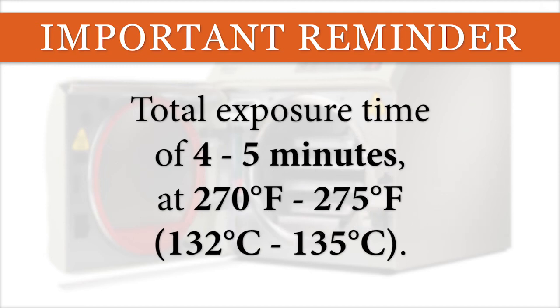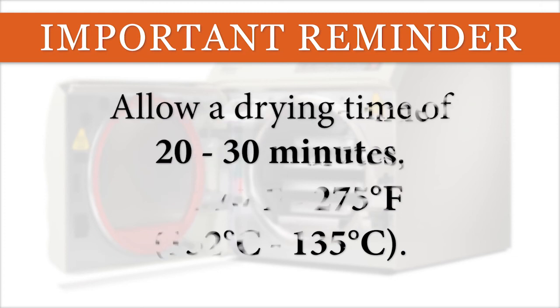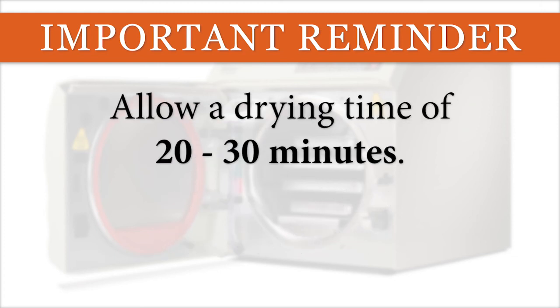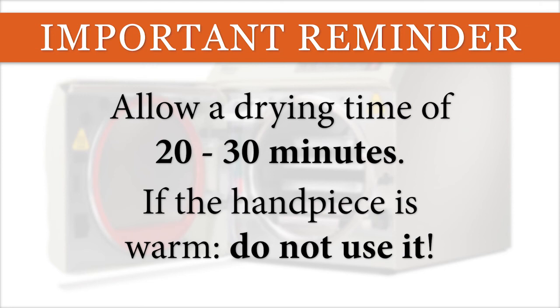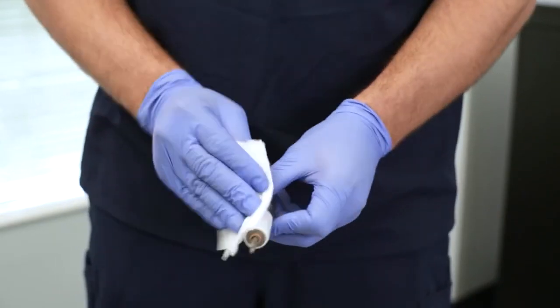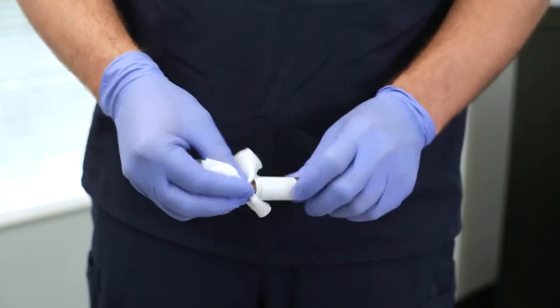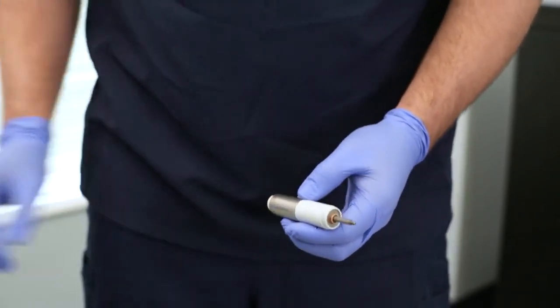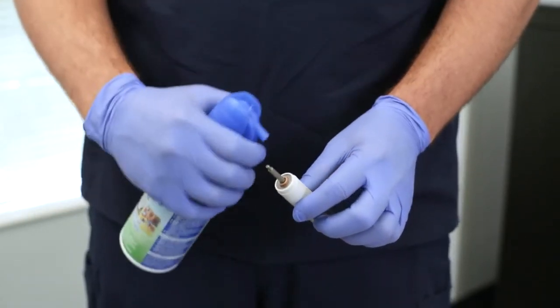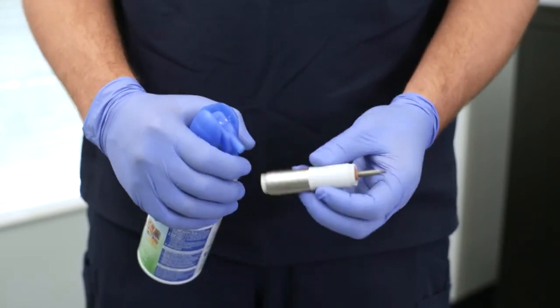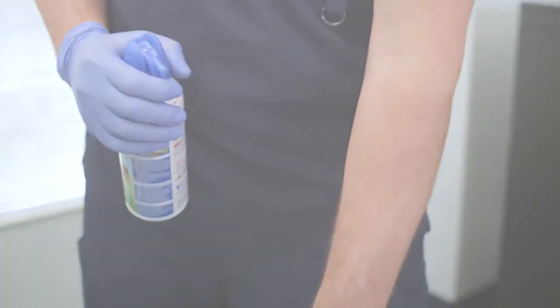Pre-vacuum autoclave for a total exposure time of 4 to 5 minutes at 270 to 275 degrees Fahrenheit, ensuring never to exceed this temperature range. Allow a drying time of 20 to 30 minutes. If the handpiece is even slightly warm, do not use it. Upon completion of the sterilization, before connecting the handpiece to the device, ensure the electrical contacts of the connector are completely dry. If needed, dry the contacts with compressed air.